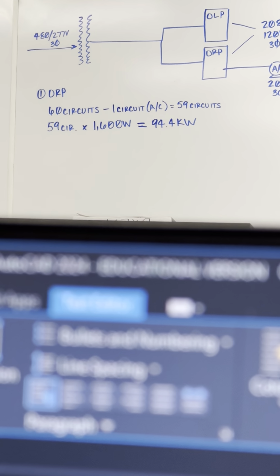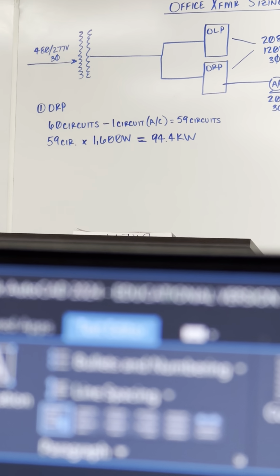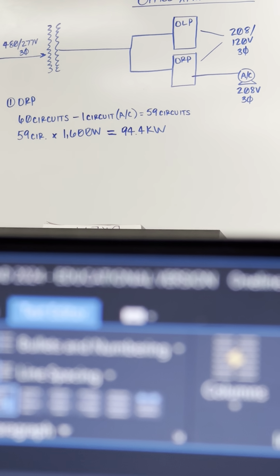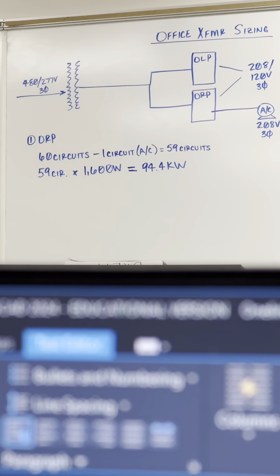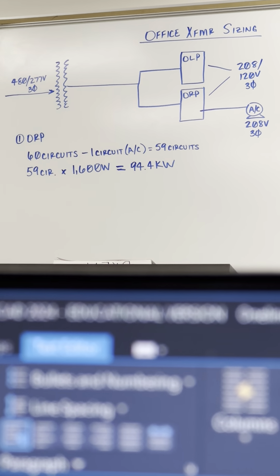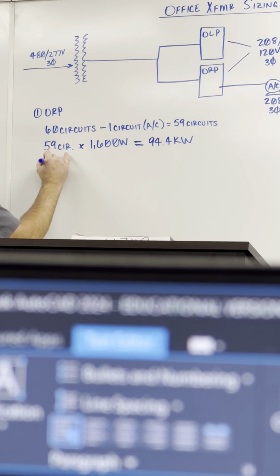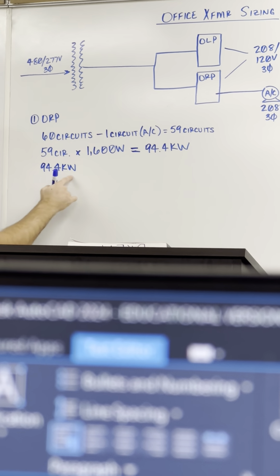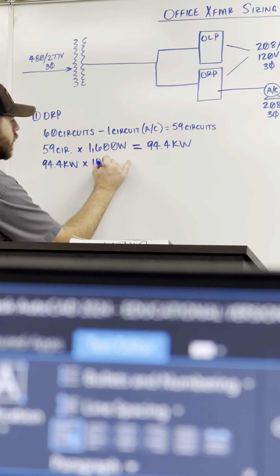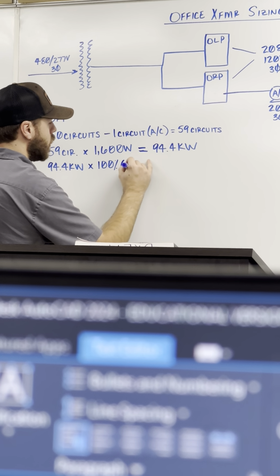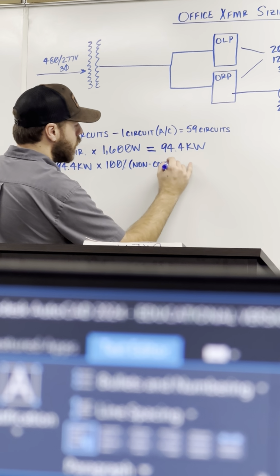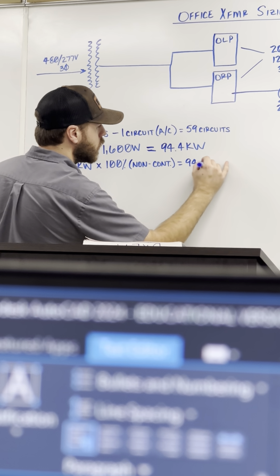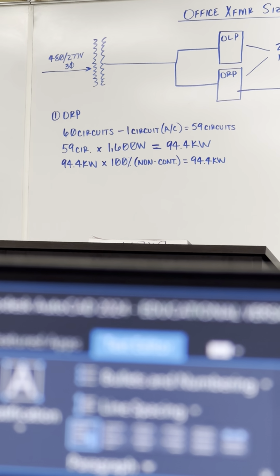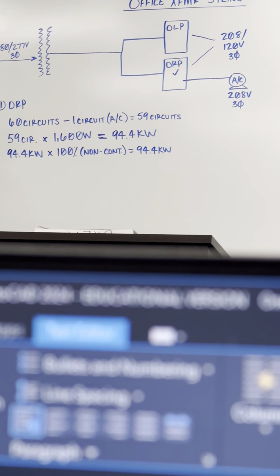Now the only little thing that we're going to add and do a little bit different here is we're going to show any continuous and non-continuous loads. So our receptacles, are they considered continuous or non-continuous? Typically not. I know you can make the argument and say, well, some receptacles are, like in here, all of our computers plug up to receptacles and I'm in here lecturing for 3 hours or more, right? But generally, receptacles are considered a non-continuous load. So we're going to show that by taking our kilowatts that we calculated, so in this example, 94.4, and we're going to multiply it by 100%. That does not change our answer any, but it's showing that this is a non-continuous load. That's our receptacle panel's load kind of taken care of.